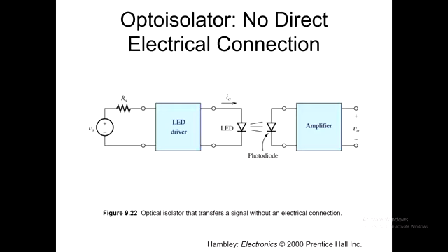If you can organise it so there's a gap in between, that can mean an electrical isolation between, say, an item that's in a hostile environment over here, that the sending signal is in a hostile environment, and here we want to be safe, so we're over on this side. Or we might have something like a vulnerable patient over this side and a hostile environment over here.